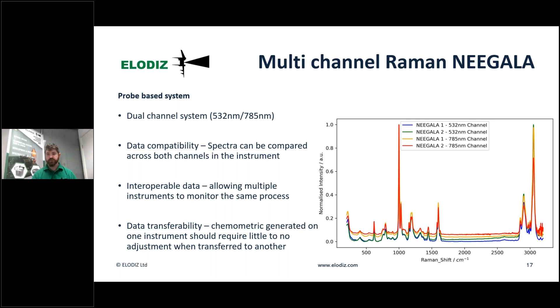Essentially, what is really important to us when developing these multi-channel Raman systems is data compatibility between those two channels. So, does the spectrum that I get from those two channels, obviously except for issues with photoluminescence effects, look the same across both channels on the same device? And then our next focus is the interoperability of the data between multiple instruments to monitor the same process. A very large industrial process would possibly want to use two or maybe three of these systems, or other Raman systems, to monitor all of the process at the same time. If there's not that level of interoperability between the data, that can cause problems in your modeling. And again, data transferability, so that chemometric models that you generate need to be able to match from one system to another to efficiently use these in process control.